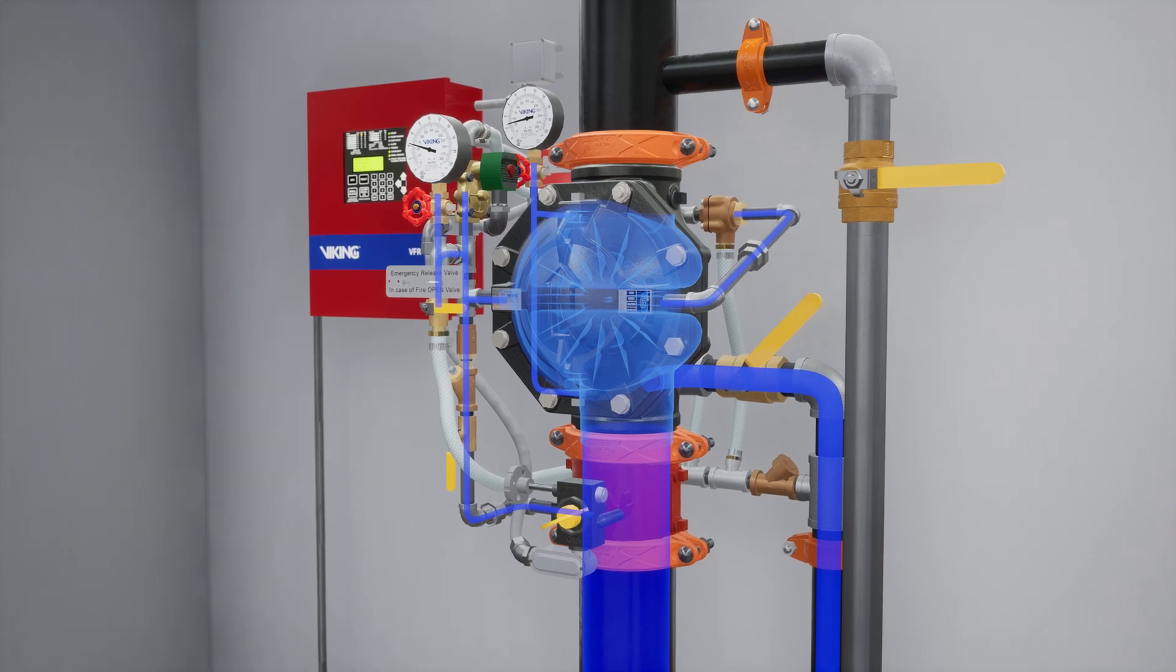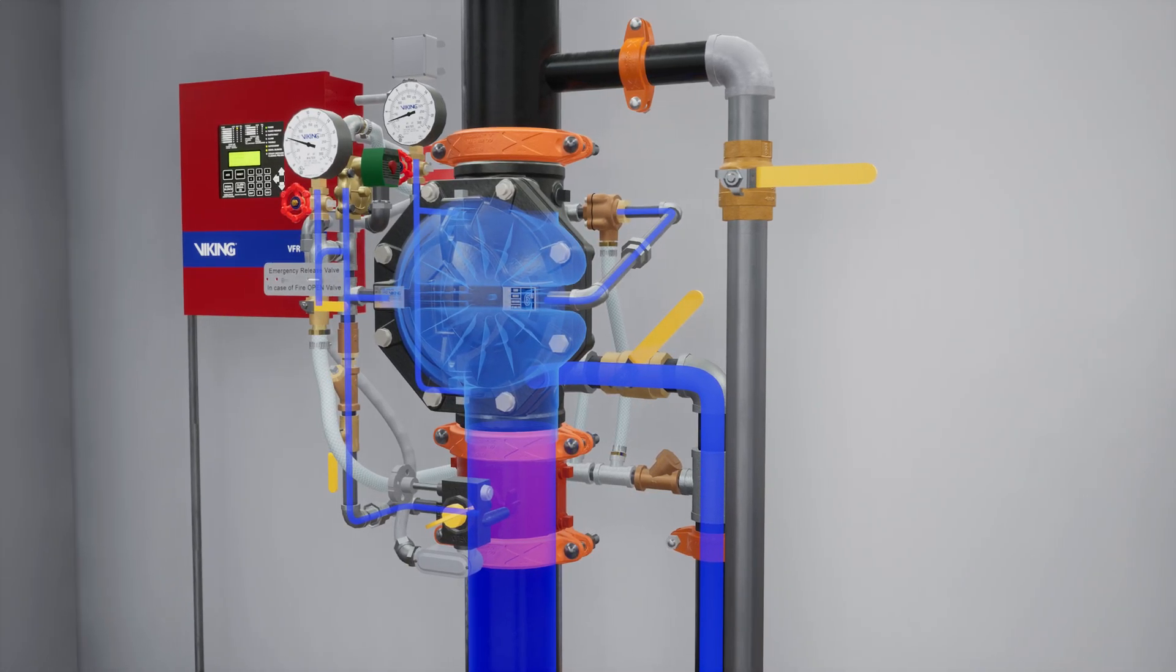Once water flow has been established, close the flow test valve. Opening the flow test valve purges any water from the inlet chamber of the VXD valve.